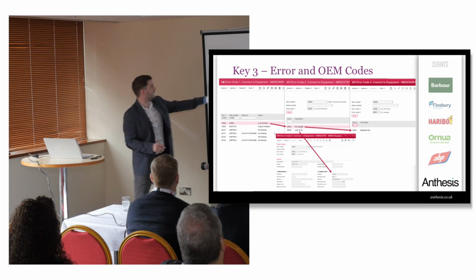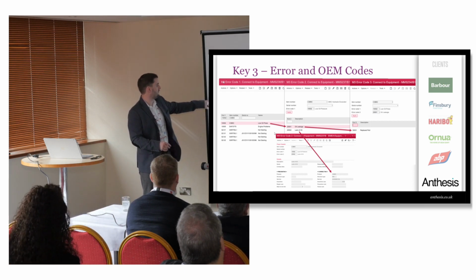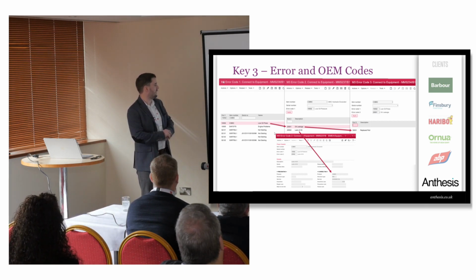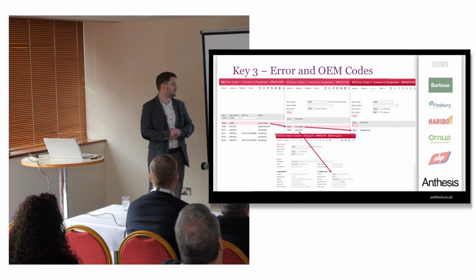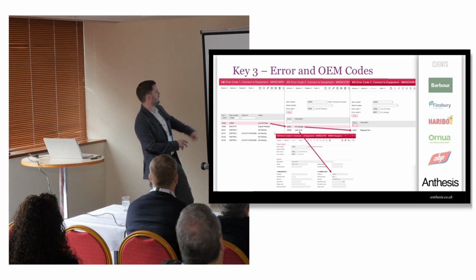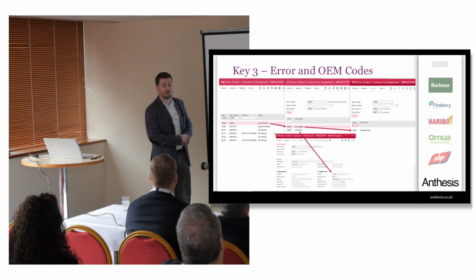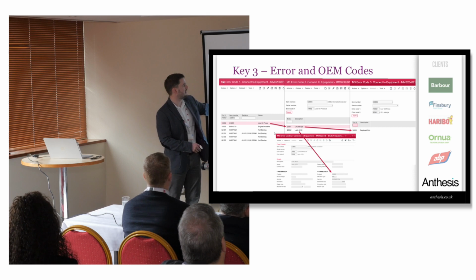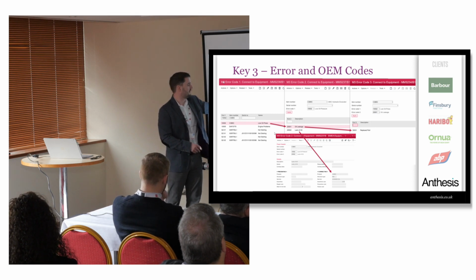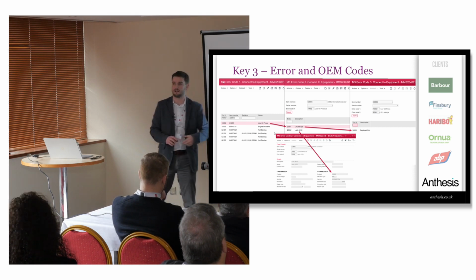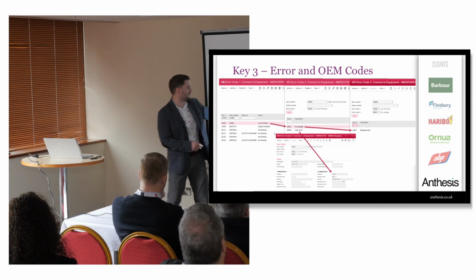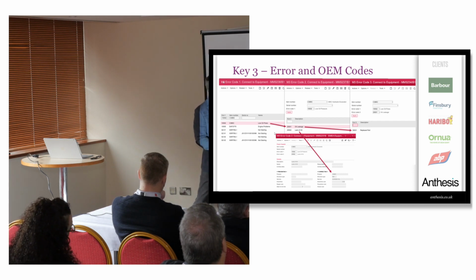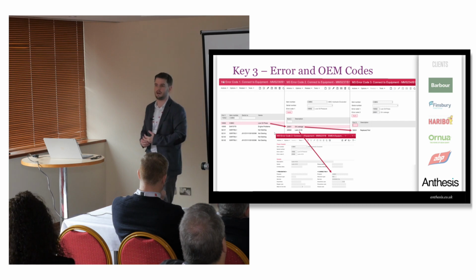Just briefly on the error codes, an example. Here for this particular item, we can limit error codes by item or even serial number in some cases. Low oil pressure was the error code, the symptom reported, and that means we now have a filtered list by making that connection - it's either oil leakage or lack of oil. Based on choosing oil leakage, we can put error code 3, replaced part.